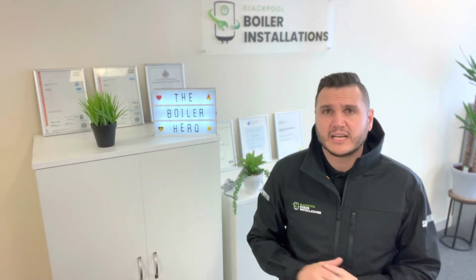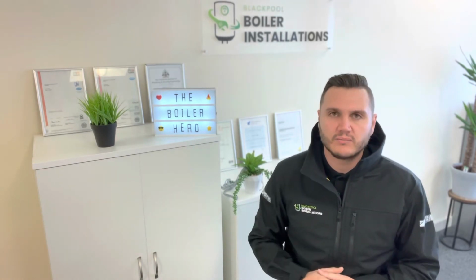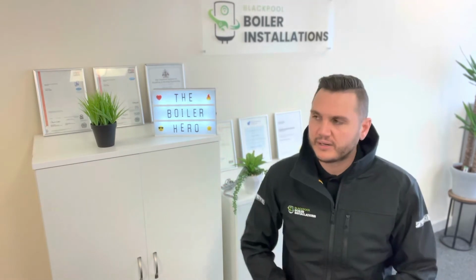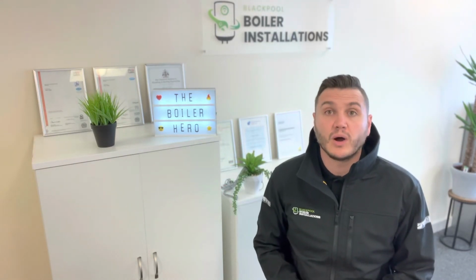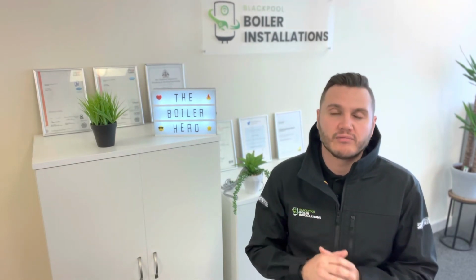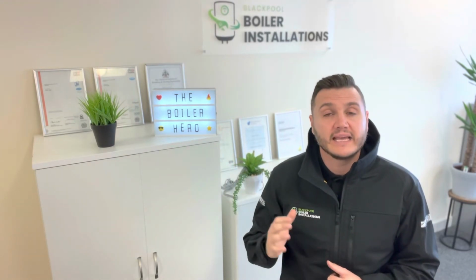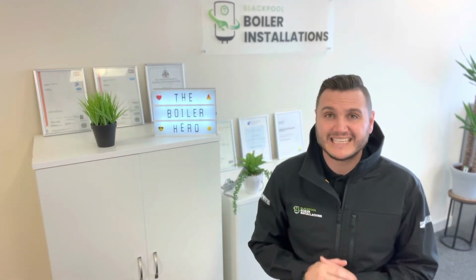Another thing that sometimes can happen is when you convert a system. Let's say you've had an old style system with a tank in the loft and an airing cupboard, and you've modernized the system for a new combi boiler. Fantastic, most people are doing that nowadays. But sometimes what can happen is because your system, your pipework and your radiators are now working with high pressure water going through them, as opposed to what you used to have, which was gravity, low pressure, you can now have leaks occur because the system can't cope with the new pressure going through it.